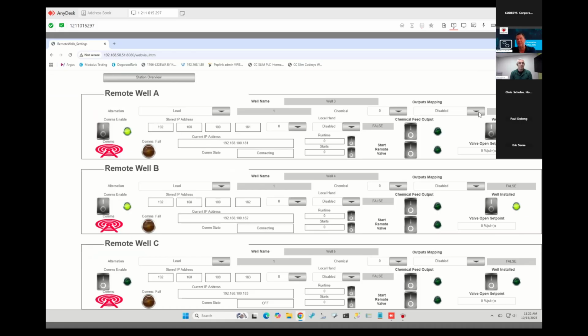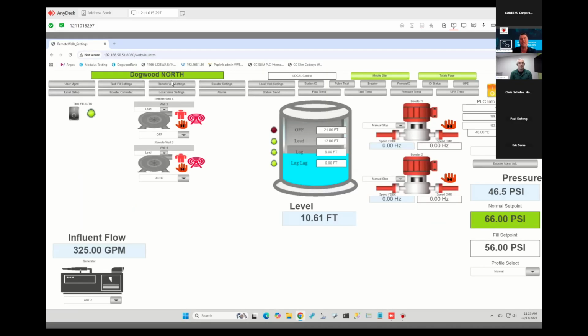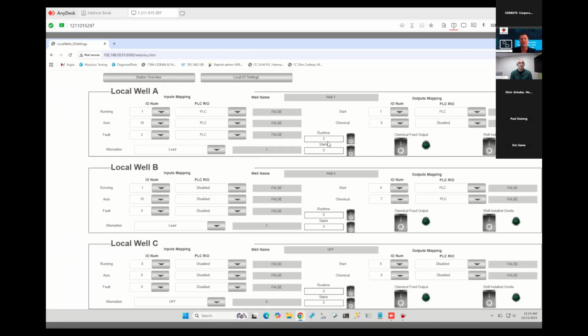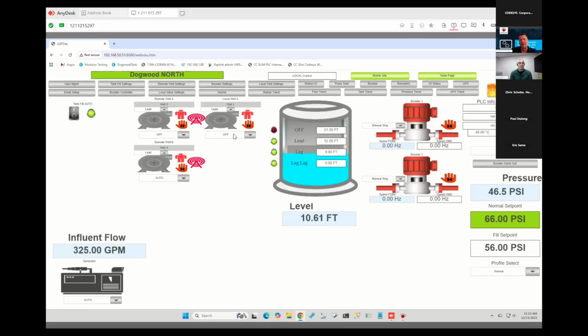So you can see disabled. In some of these systems, the remote well feeds in, but the chemical feed is at the tank site. So this allows you now to come here and set a PLC output to feed chemicals whenever this well is running. So the customer can configure completely what he wants in this system. So if we go in and we set a new local well, same thing, we could run a chemical pump off of it, map all our IO. Now I've got a new local well here also. And the system will stage those in and out as it needs to.